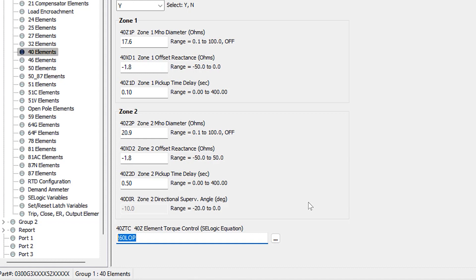The last setting here is 40ZTC — the torque control for this loss of field protection scheme. This means the relay will allow the loss of field elements to operate only if this condition is a logical one. I'm going to leave this at the default setting, which is NOT 60LOP, meaning there is no loss of potential condition. Relay word bit 60LOP indicates an issue with the PT circuit, and you don't want to trip when there's a PT circuit issue.